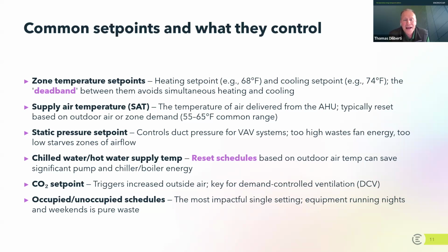In theory, what the reset schedule is, it's a way for the building to adjust the chill water or hot water temperature to reflect the real need in the building, whether you're needing to heat a lot or cool a lot. And I've got some examples of that coming up as well. There's the CO2 set point. So again, this triggers ventilation systems to increase or decrease their flow if you get out of set point range. And then it's the occupied and unoccupied schedules.